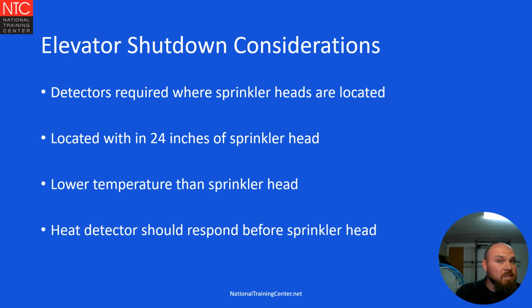Some things to take into consideration with elevator shutdown. Detectors are required where sprinkler heads are located. We want to have those detectors within 24 inches of the sprinkler head itself, but at a lower temperature than the sprinkler head, because again, we want shutdown to happen first. Heat detector should respond before the sprinkler head.